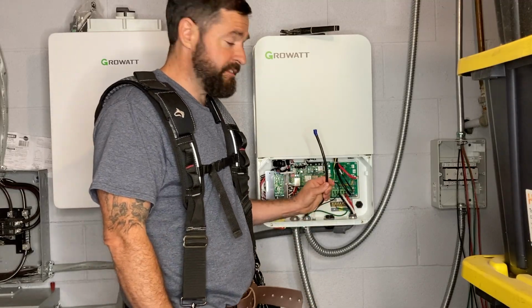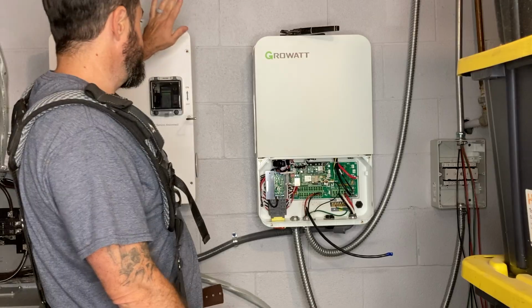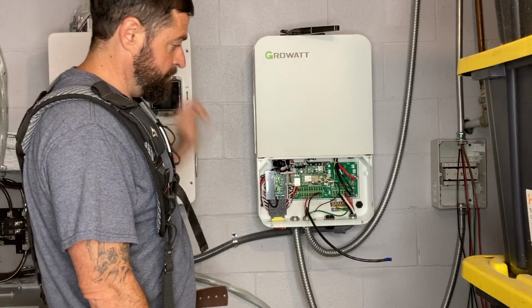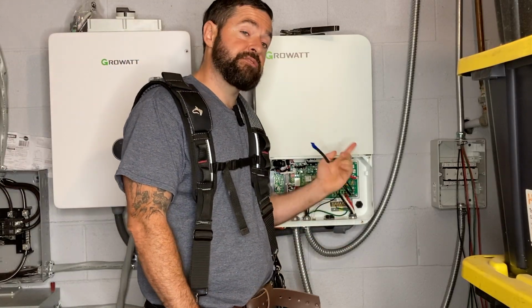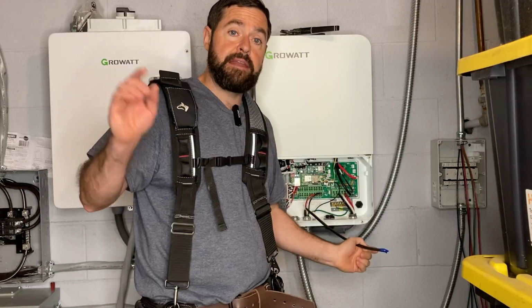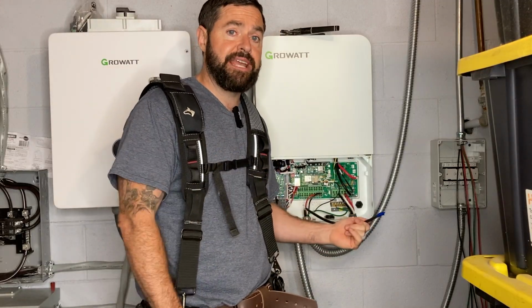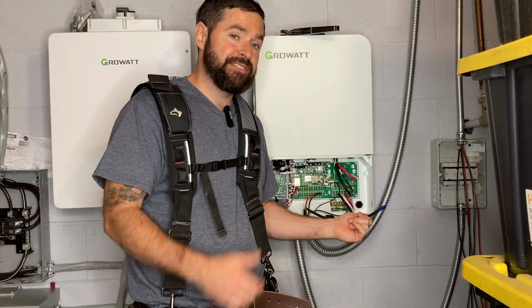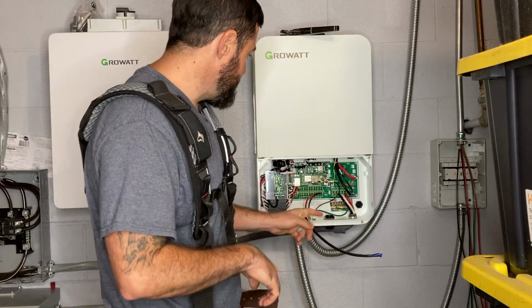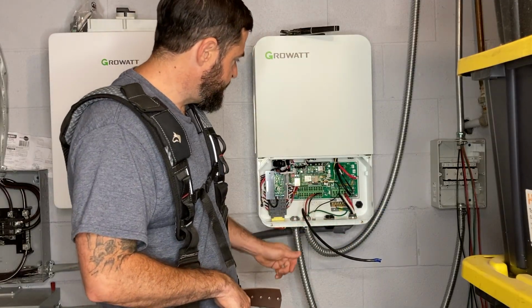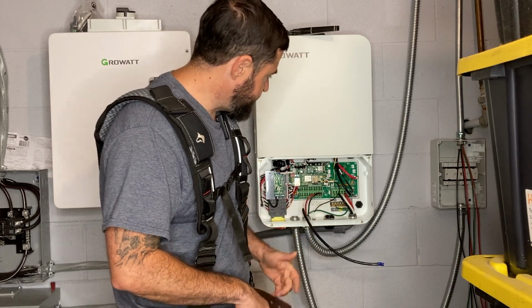You do want to use this between the inverter and the MID, but for the communications between the inverter and the battery, you want to just pull standard Cat 5 cable, because it does require a little Cat 5 crimp here on the Growatt side of things, where it plugs into the circuit board.